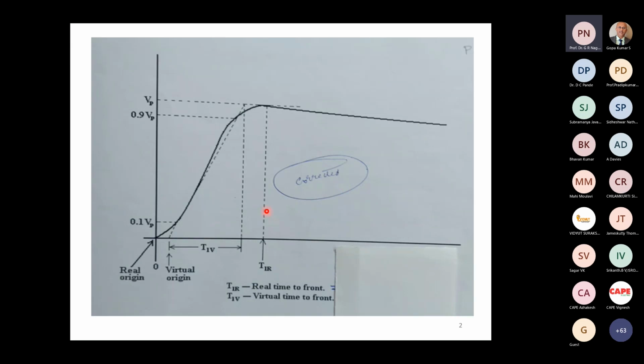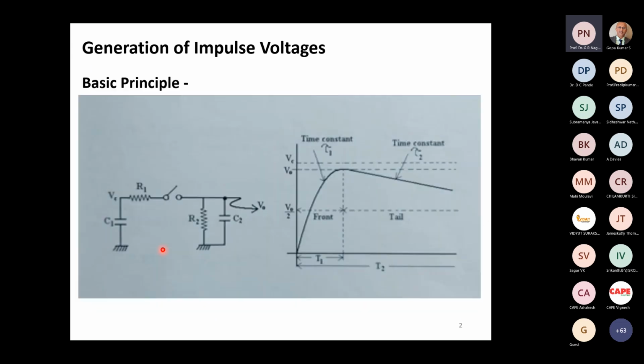Now, particularly in earlier times, when you did a test on any equipment in the laboratory, the 0 was not easy to identify. Therefore, what was done was they identified the 10% of the peak value and 90% of the peak value, joined the two, and extended the line to the peak value. And the time between these 2 points is known as the virtual time to front, and that is what we call the virtual time to front of 1.2 microsecond plus minus 30%. And this gives us a slightly longer real time to front, 0 to peak, typically around 1.7 to 1.8 microseconds. On the tail again, this 0 is immaterial because there is 50 microseconds. A small variation here is not of great importance.